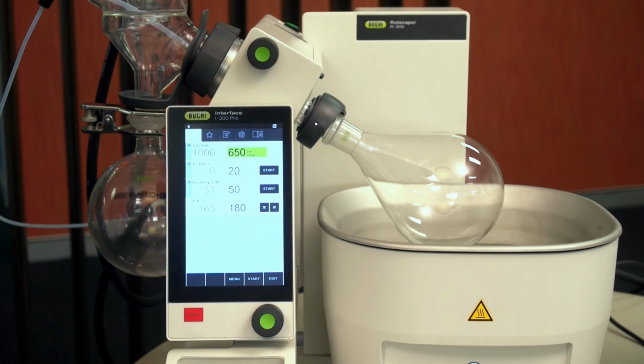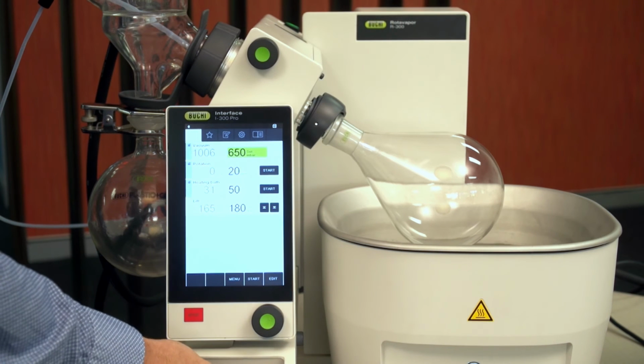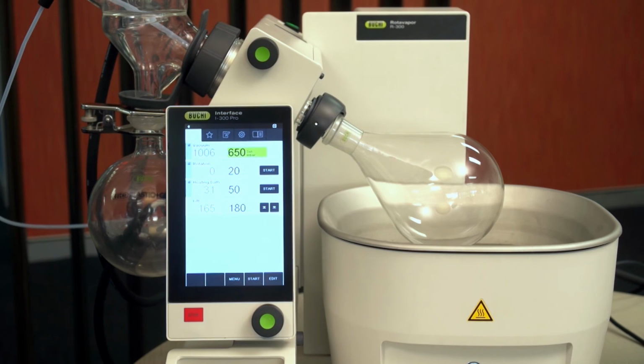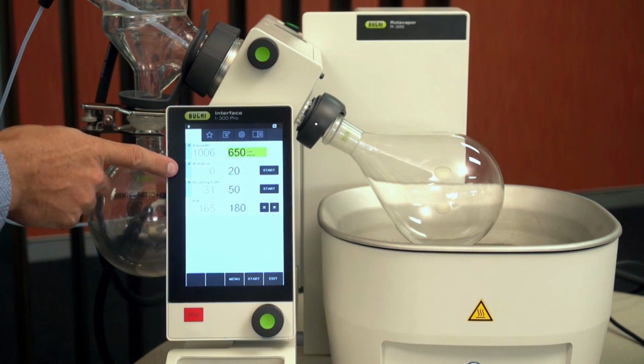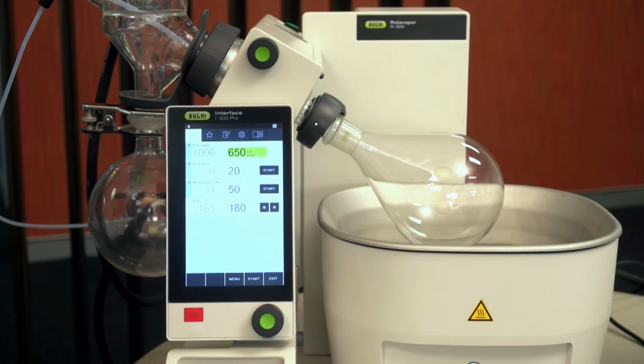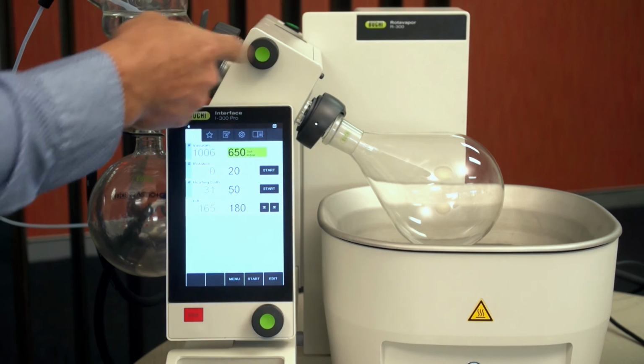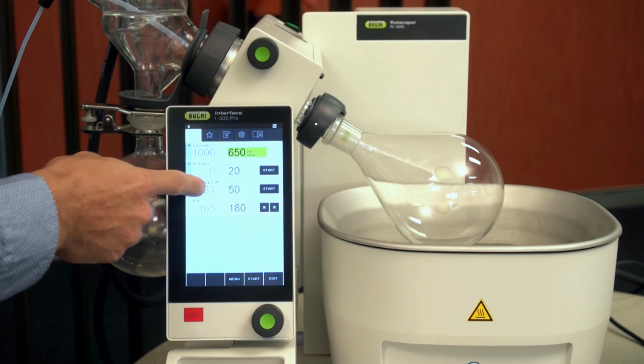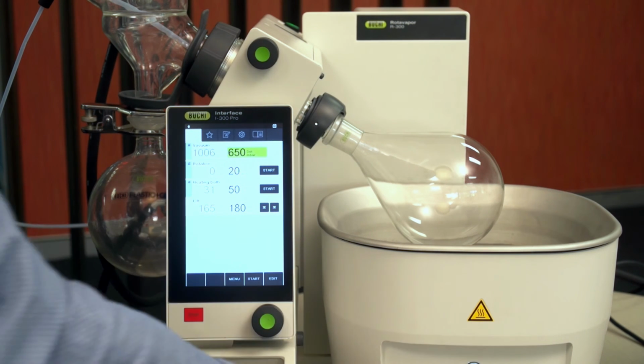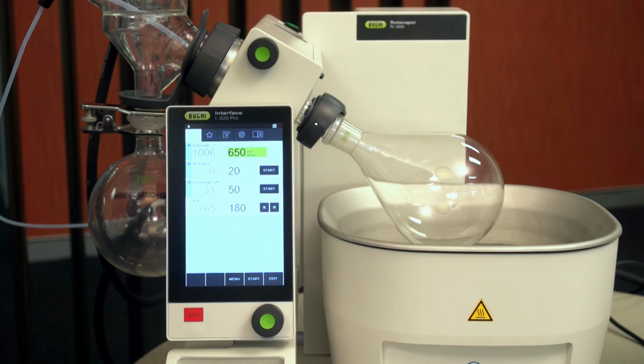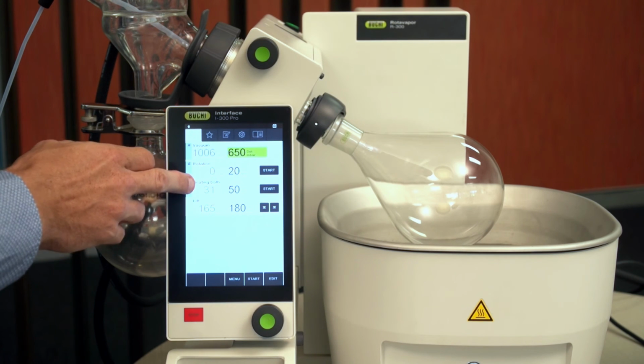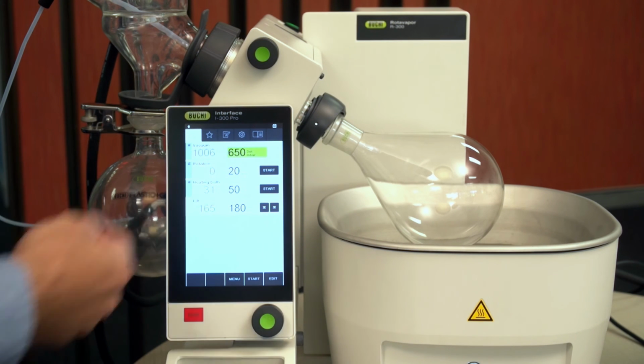Using the Buchi I300 Pro touchscreen interface, it is also possible to mount it on the front of the electronic R300 rotary evaporator. You will notice there are a few additional parameters on here. We can set the rotation, or the RPM, for the drying flask. We can set the heating bath temperature, and this will also relate to what is being shown on the display down on the heating bath here. Our actual temperature at the moment is 31 degrees. It is set at 50.